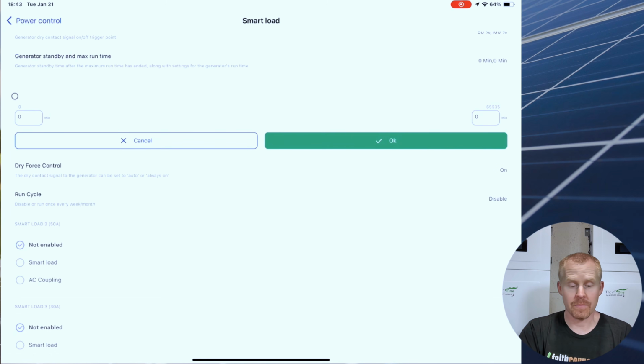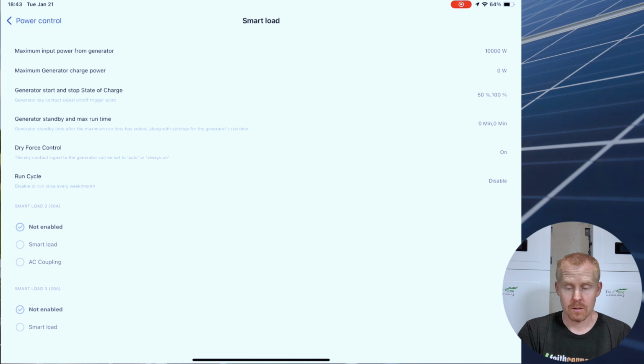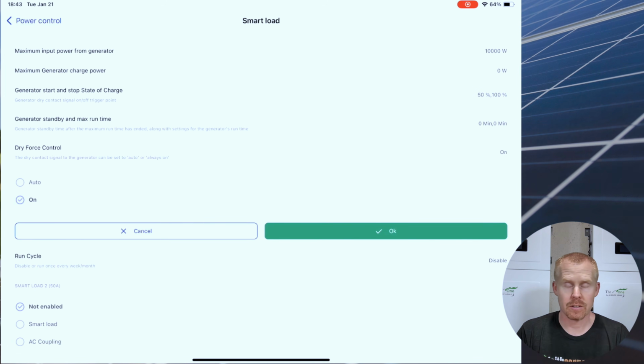If you're using an actual generator, you can set a maximum runtime. Dry force. Do you want to turn the generator on regardless of the state of charge? If it's on auto, then it's going to follow the state of charge or the voltage, depending on how the system is set up. If it's set to on, then it's going to immediately switch over to that generator and supply power to all your loads from the generator.